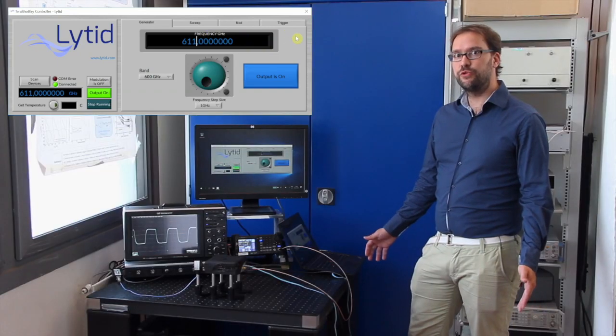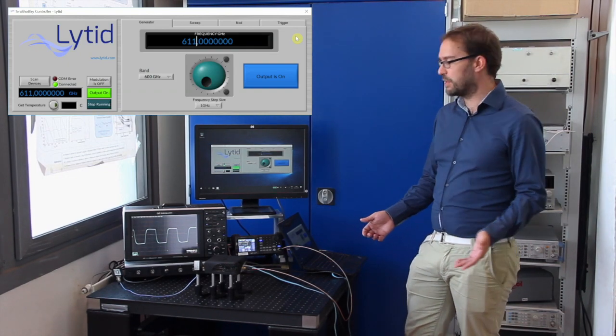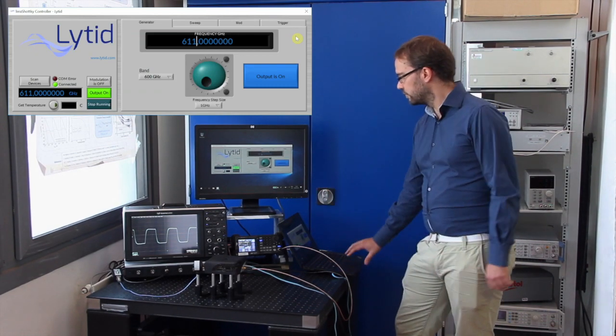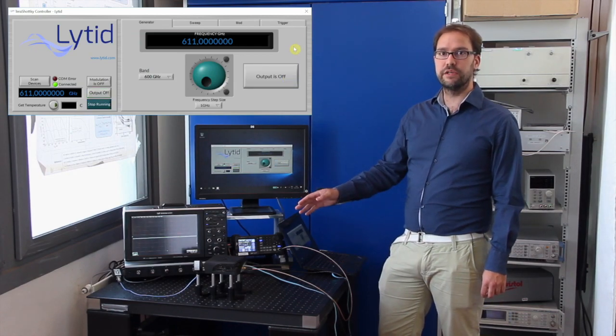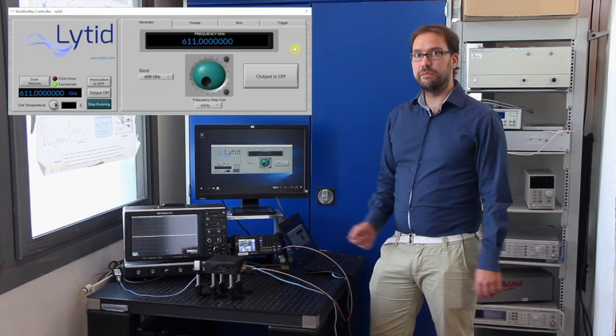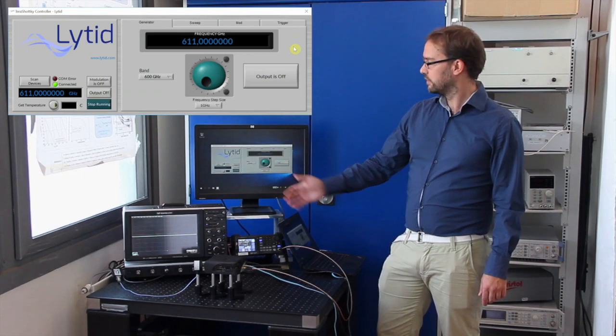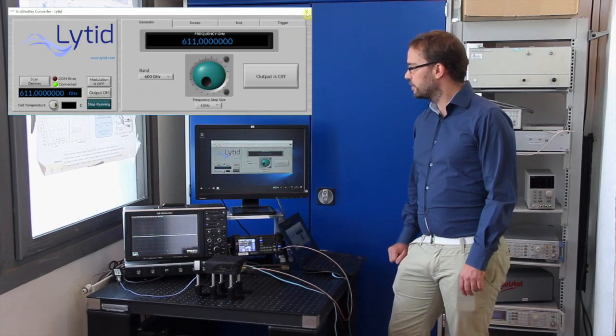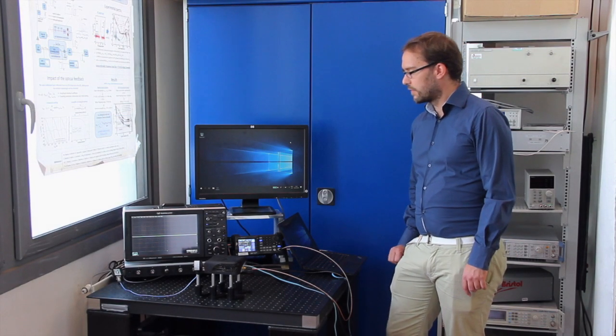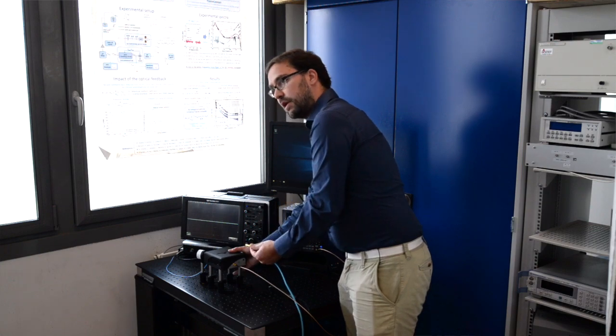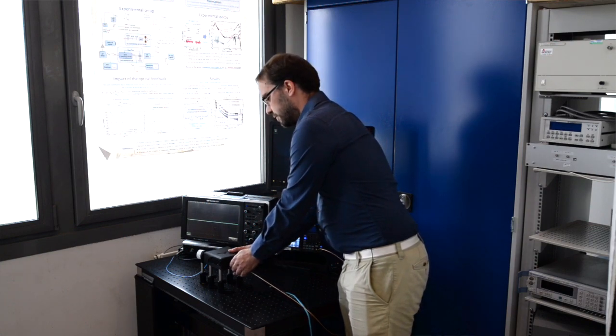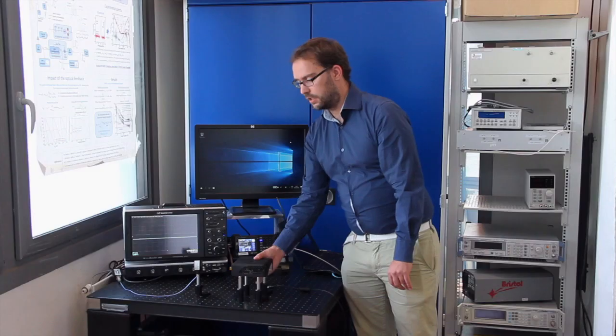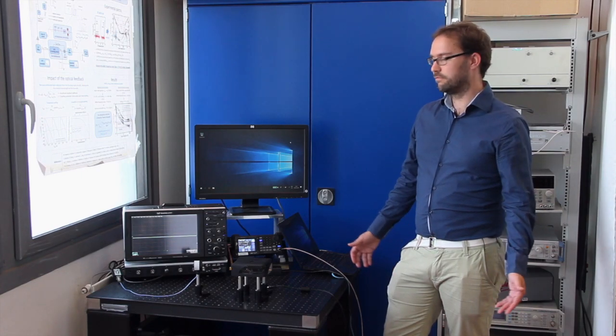Finally, I will show you how to shut down the source. At the end of the day or when you're finished doing measurements, most importantly the first step is to put the source off. This will cut down the RF synthesizer, so no RF will be fed through the multiplier chain. The output will be off. And only at this point you can close the software. And finally, unplug the DC power supply, the micro USB connector, and the SMA signal for trigger. And the source is off. And that's it.